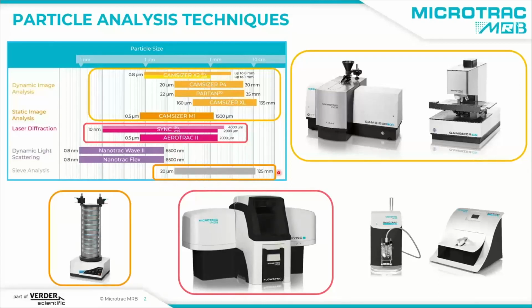Most of you will be familiar with another method of particle analysis that is classical or traditional sieve analysis. Sieve analysis is very common, but you are always limited to the number of sieves that you have if you want to get a size distribution. And in many cases, this is not good enough in terms of accuracy and resolution. Also, the sieves have tolerances. So people are looking for more automated, more accurate, and more reproducible technologies like laser diffraction or image analysis.